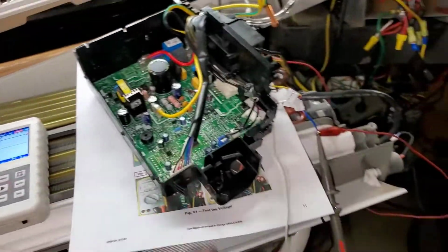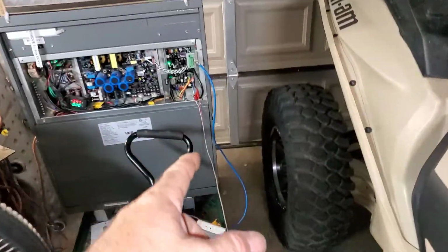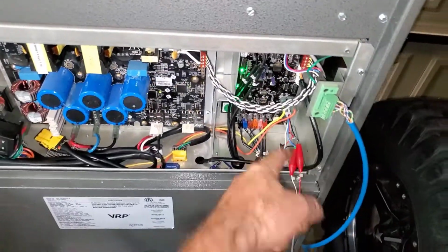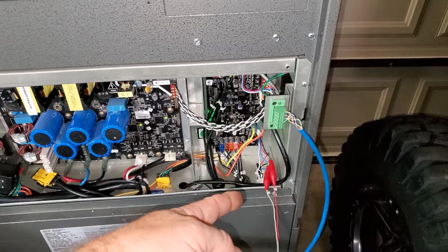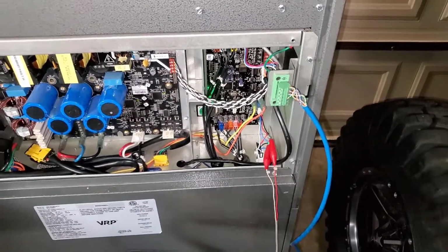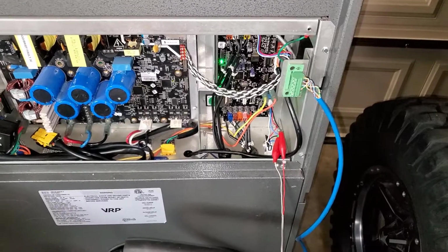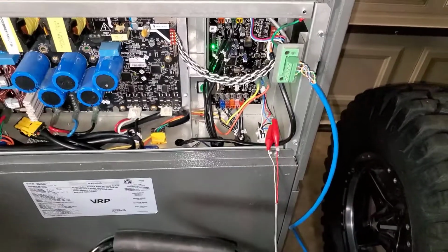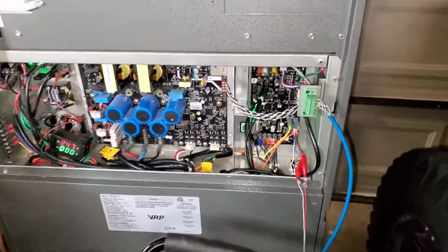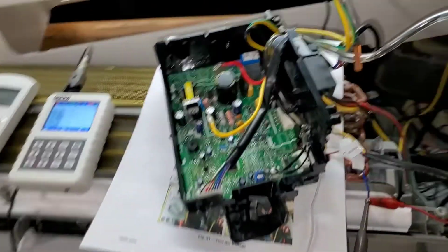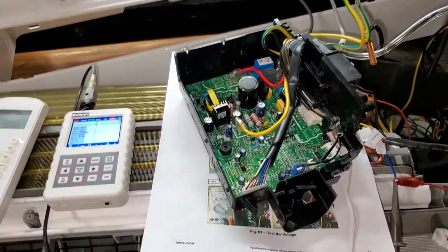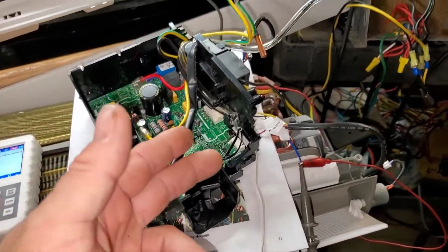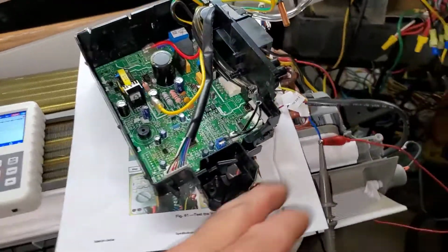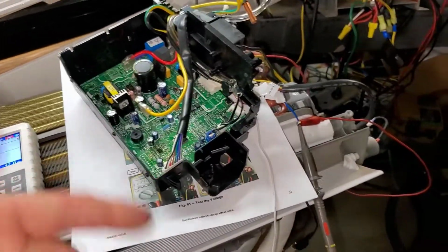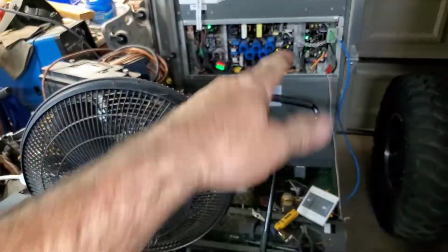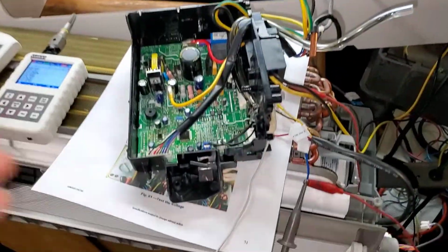So I'm just looking at the speed reference. Again, I will have to interface something to put pulses into this ECM board. When that blower is running, it needs to know that the blower is running. So hopefully it's not too dependent on what the frequency is exactly, other than just knowing that the motor is running. It's pretty much just a fan proving switch, I hope, and doesn't do any other real speed control feedback. If that's the case, I might even be able to just take the signal out of this, if it's enough, and go into an optical isolator, and then take the output of that optical isolator, take its own power and switch it right back into itself to make the pulses over there.